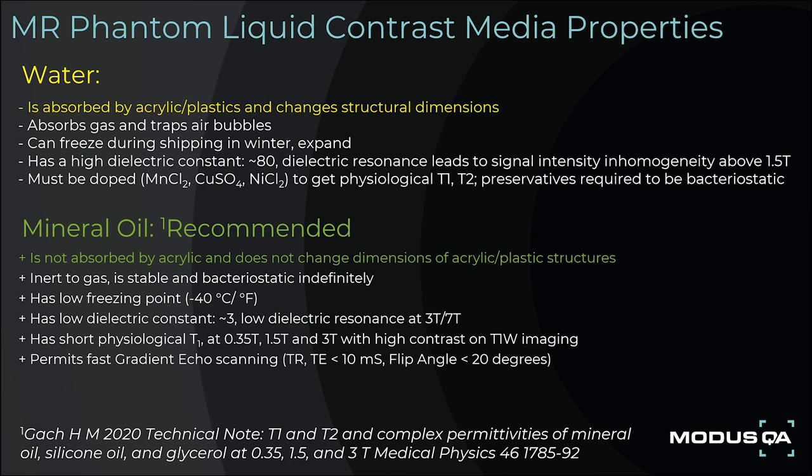Mineral oil, which is highly recommended, is not absorbed by acrylic and does not change dimensions of acrylic or plastic structures. It is inert to gas, stable and bacteriostatic, has a low freezing point, a low dielectric constant making it suitable for use at 3 T and even 7 T, has a short physiological T1 at all field strengths from 0.35 T to 3 T with high contrast on T1 weighted imaging, and it permits fast gradient echo scanning.